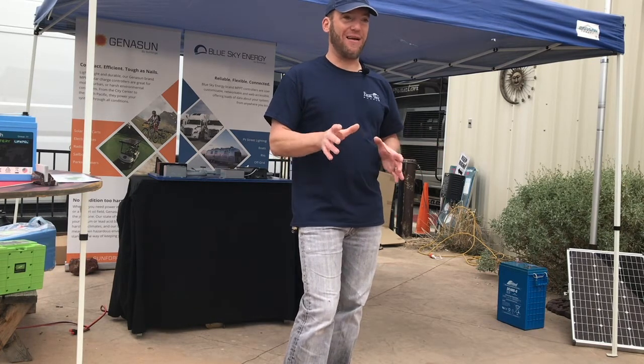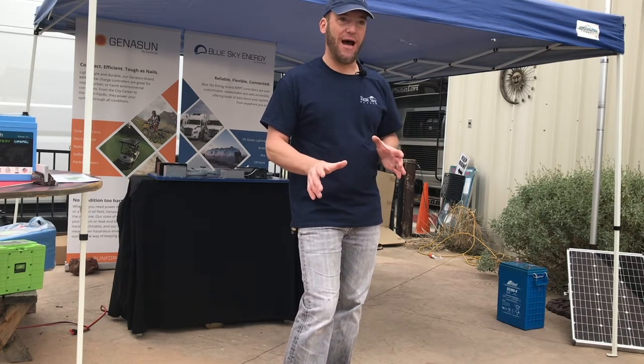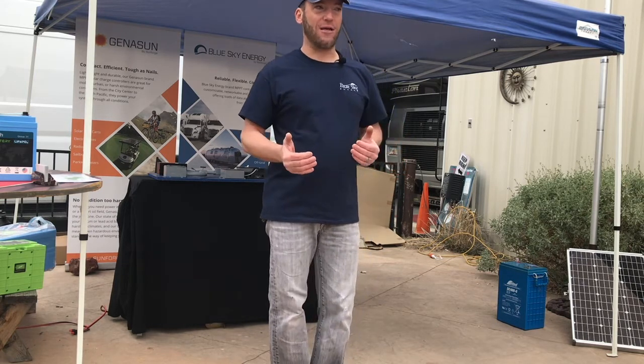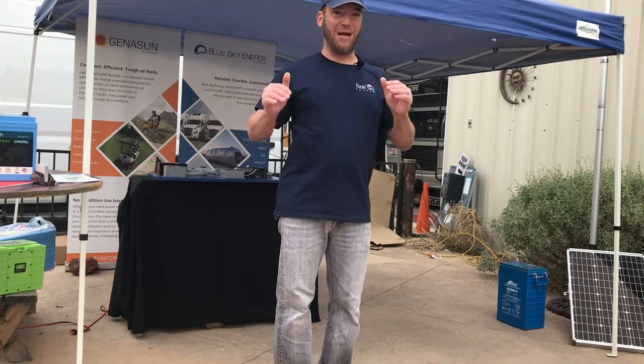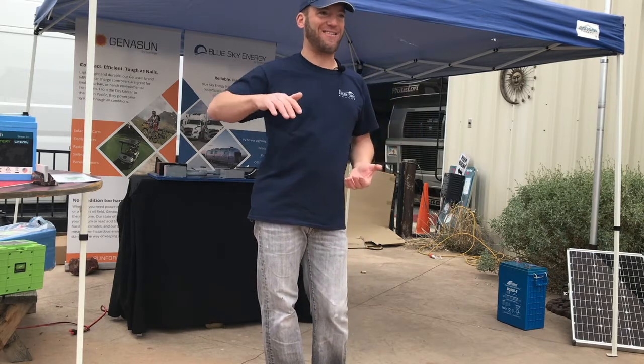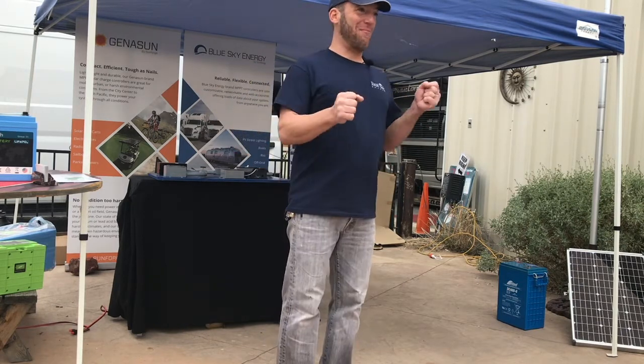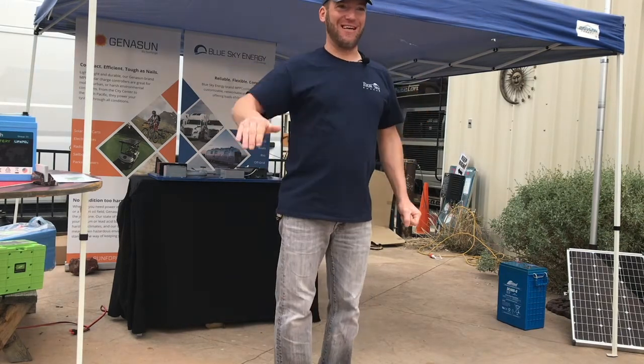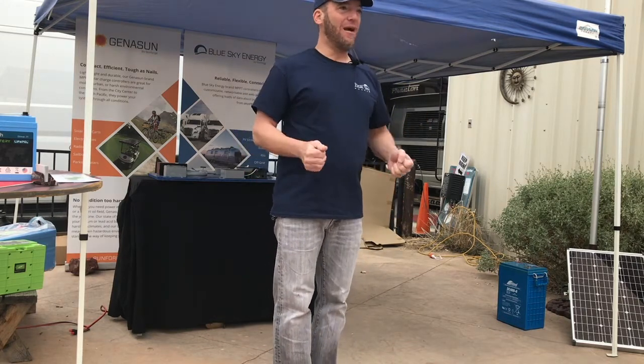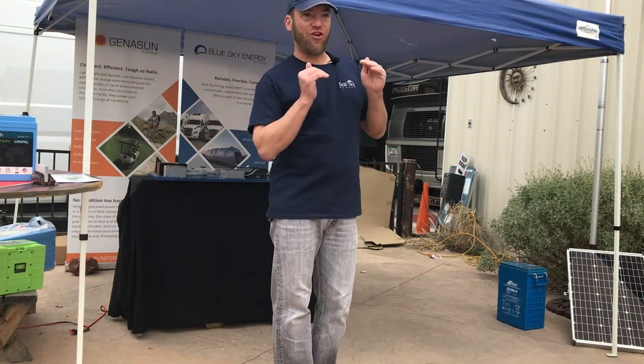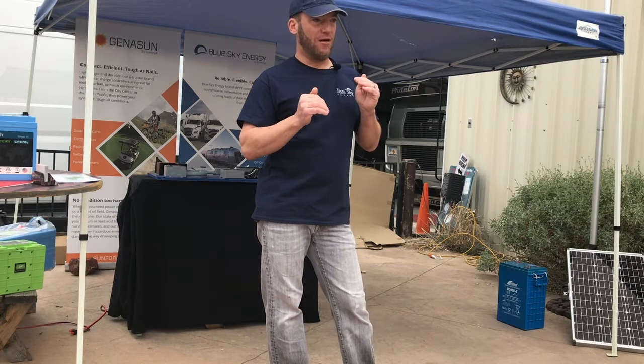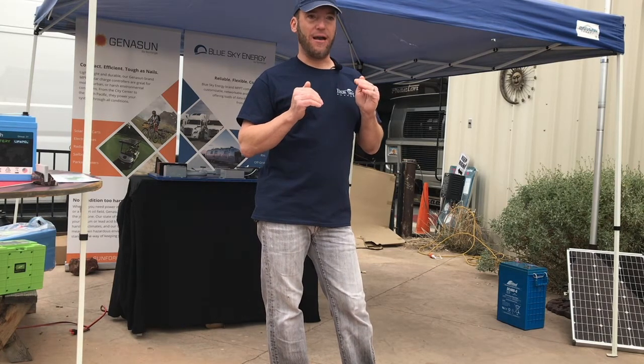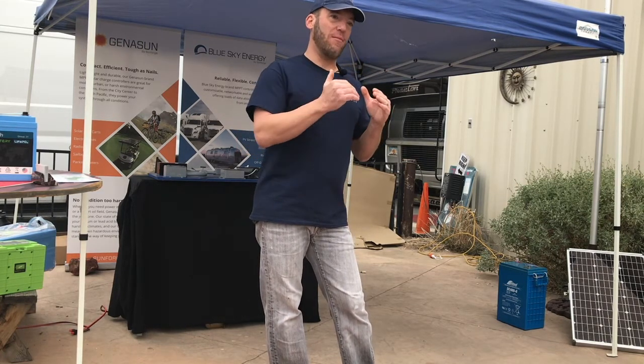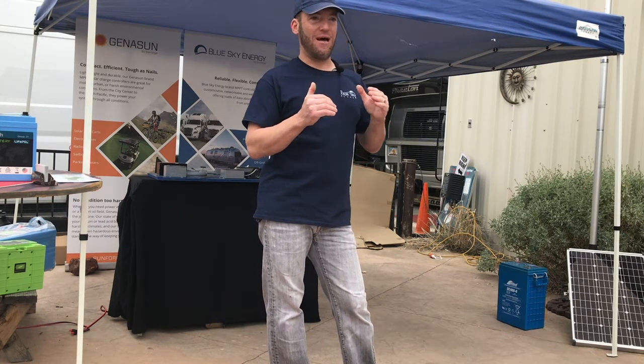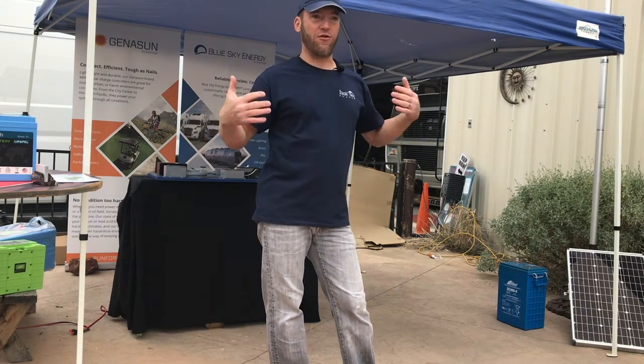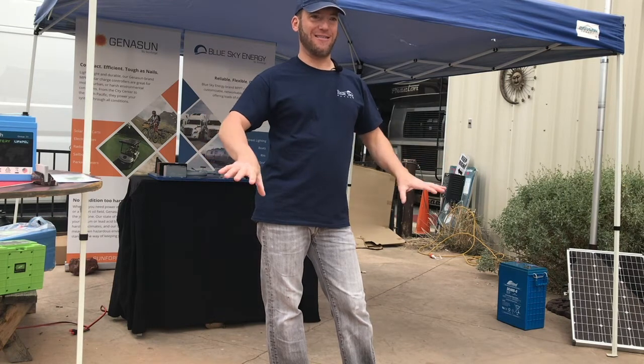After two weeks, it'll settle down to like 13.4, 13.4 and a half. So you do need to have a float voltage, because you have to pick some point to take care of your loads prior to the sun setting. It doesn't do any good to charge your battery just to discharge it until the sun sets. So you charge the battery, and then you pick a float voltage just underneath the resting voltage of the lithium battery, so you're not providing current to maintain that voltage, but at the same time you're supplementing all your usage in your rig until the sun sets.